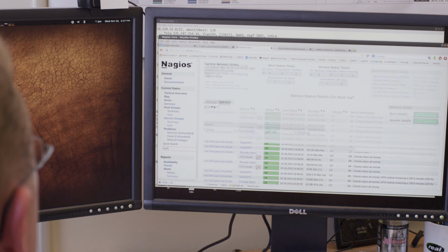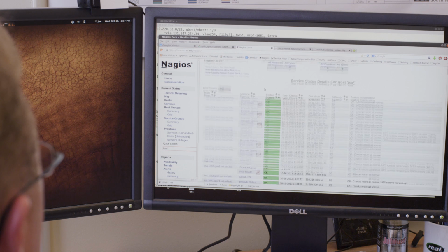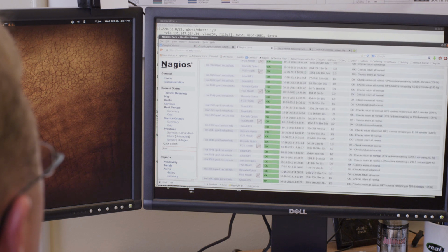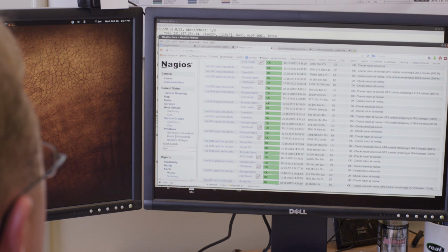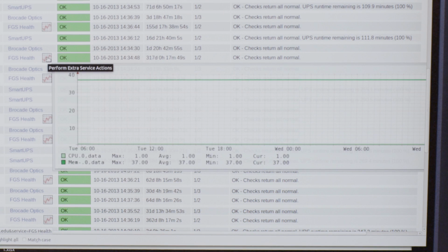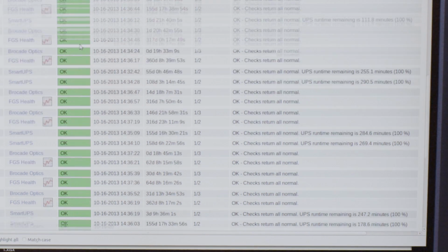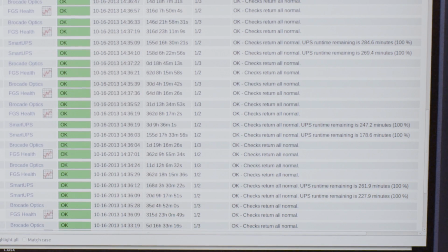So the network engineering group runs software to monitor every one of these devices. We check their availability and health every 3 minutes. We check things like CPU, memory utilization, optical power levels on the fiber links, room temperatures, UPS capacity, and general functionality of the device. If any of these parameters are out of normal values, we are notified and someone from the operations or engineering group will troubleshoot the issue.